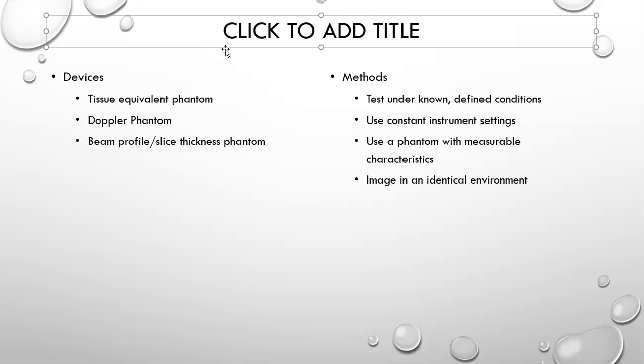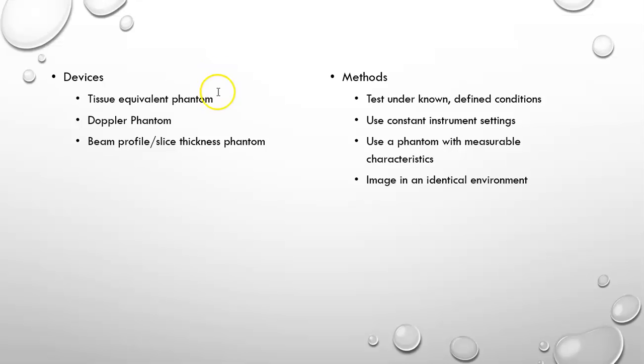The types of devices that we're going to use in any quality assurance program include tissue equivalent phantoms, Doppler phantoms, and beam thickness or profile phantoms. Of these three, I'll just say that very few quality assurance programs look at the beam profile. And you guys already know how to do this using a rubber band and an angle iron, because we did this in the lab. So you could potentially make your own slice thickness phantom. And also, for the Doppler phantoms, there are no approved Doppler phantoms on the market yet. They all have some problems with them, though there are some that are useful, and we'll talk about their limitations and why they're not approved later.